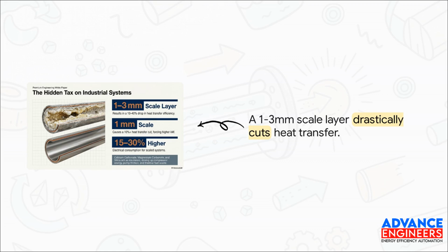Just a tiny 1 to 3 millimeter layer of calcium carbonate inside a shell and tube heat exchanger causes a staggering 10 to 40% drop in heat transfer efficiency. Literally 1 single millimeter cuts your heat transfer by over 10%. To put that into perspective, the thermal conductivity of this scale is roughly 8 times worse than stainless steel. The heat simply cannot pass through it effectively.